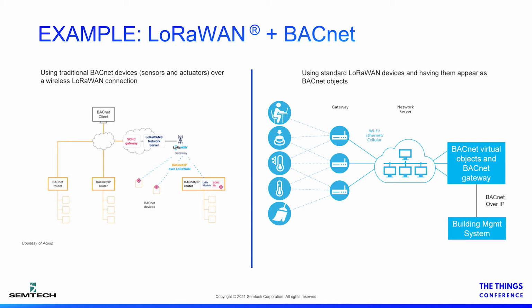A small standardized adaptation layer called SCHC is used to fragment and compress the BACnet over IP traffic in a way that can now be carried over LoRaWAN packets. This can be done either directly at the device or in a BACnet over IP router, which connects to a number of different BACnet devices.